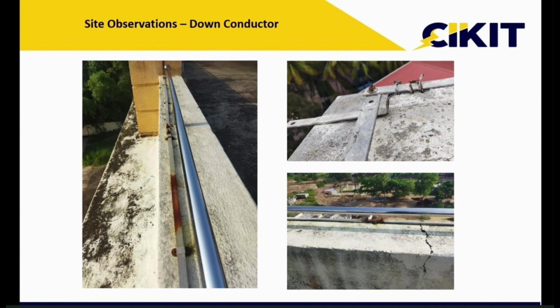So if you have many metallic structures near this down conductor, they should be connected to maintain uniform potential. If uniform potential is not maintained, then there will be a flashover between this lightning conductor and the other metallic parts. It may result in a huge explosion or accident also. Here, the equipotential bonding is not done properly. And in the second image, the connection was made using a steel rope. That is not at all advisable.